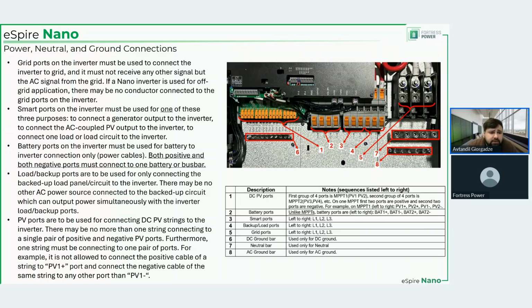Also, important things to note. If you connect PV1 plus and PV1 minus to one MPPT, use 1 pair each, because that is easier for you and that is safer for the system. So if you have PV1 plus and PV1 minus for the first, and PV2 plus and PV2 minus, the pluses and minuses must be grouped together. So one string's plus and one string's minus goes to 1 plus and 1 minus. Not like positive goes to 1 plus, but the negative goes to 2 minus. Please avoid doing that. It's not a good practice. Other than that, you see what you see on the screen.